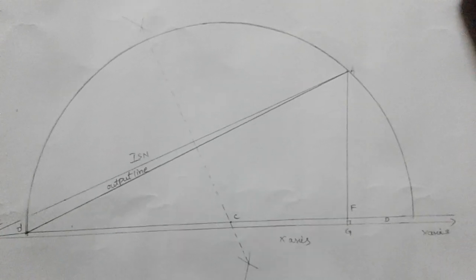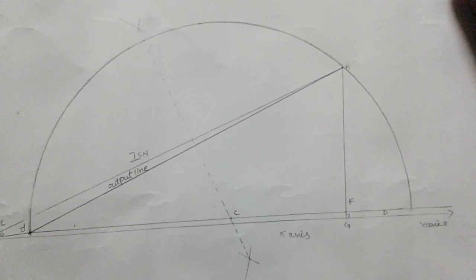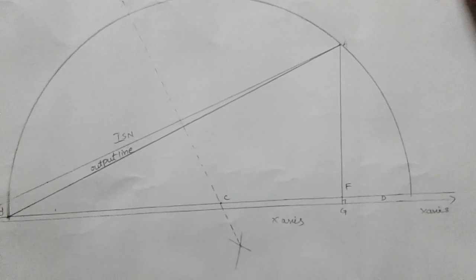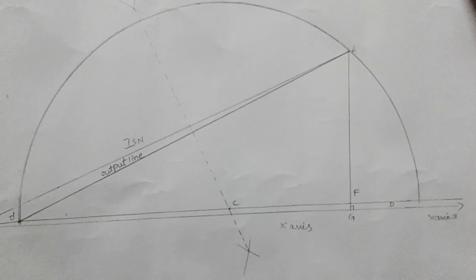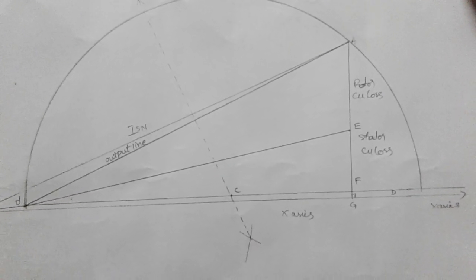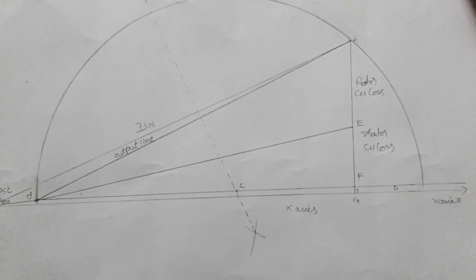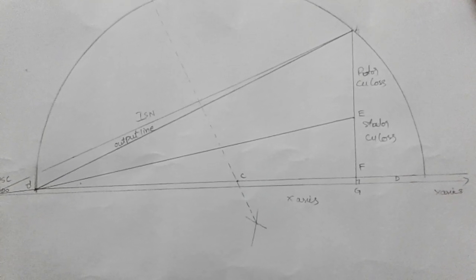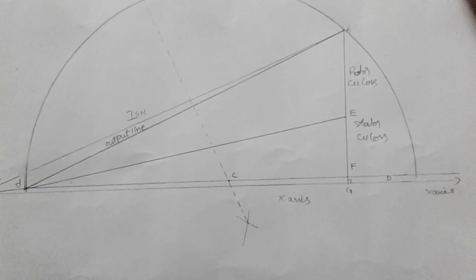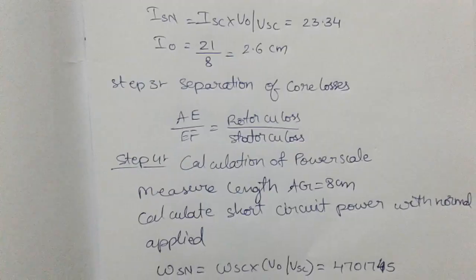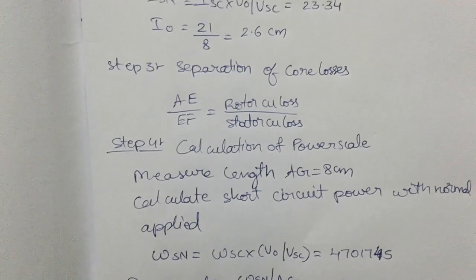Point D is the intersection of the X-axis and the parallel line, indicating fixed losses. To calculate the stator copper loss, measure the AG distance, find its midpoint, and join that midpoint to O'. After calculating AF and dividing it in half, mark the midpoint as E and join it to O'. The upper part AE indicates the rotor copper loss, and EF indicates the stator copper loss. The segment FG indicates the fixed losses.